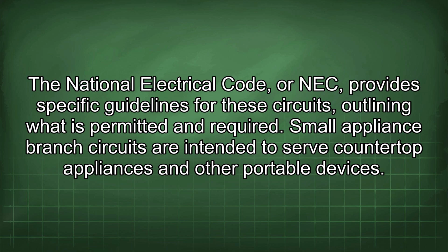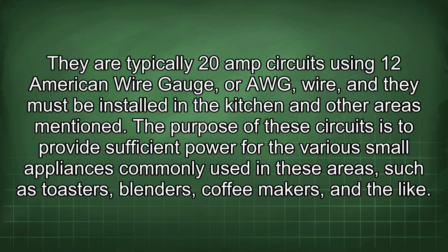Small appliance branch circuits are intended to serve countertop appliances and other portable devices. They are typically 20-amp circuits using 12 American wire gauge, or AWG, wire, and they must be installed in the kitchen and other areas mentioned. The purpose of these circuits is to provide sufficient power for the various small appliances commonly used in these areas, such as toasters, blenders, coffee makers, and the like.